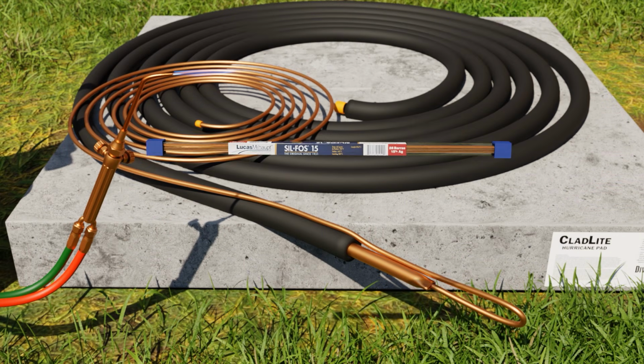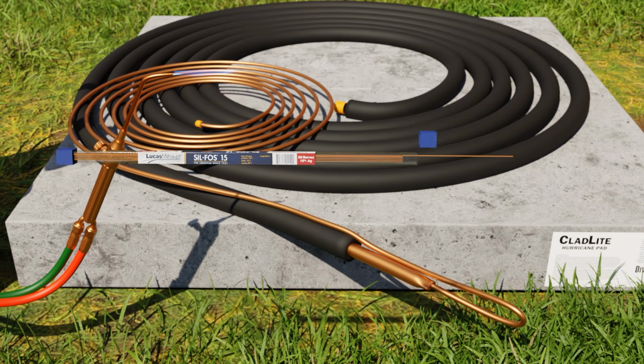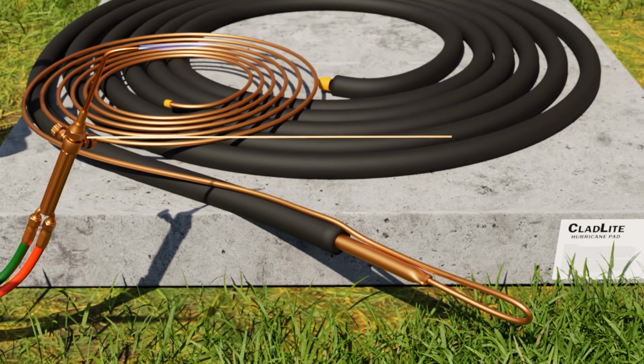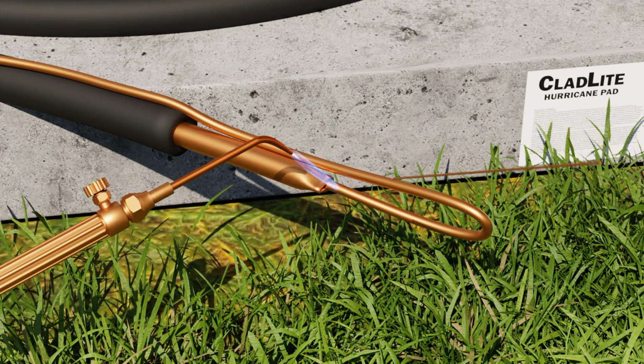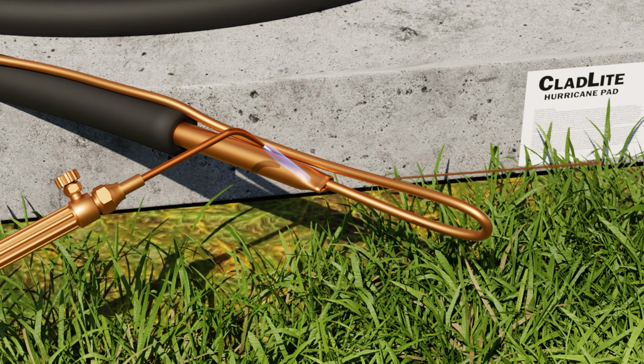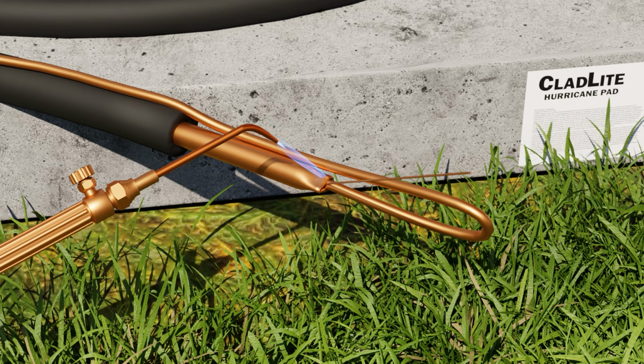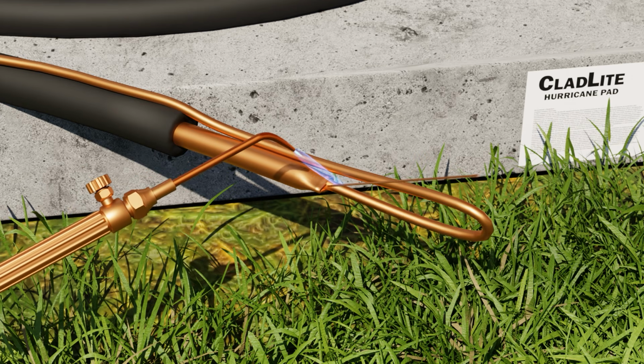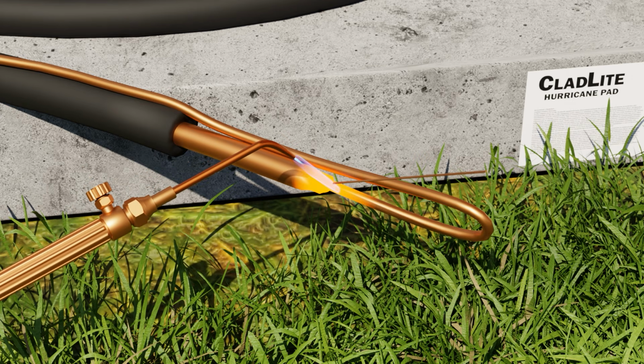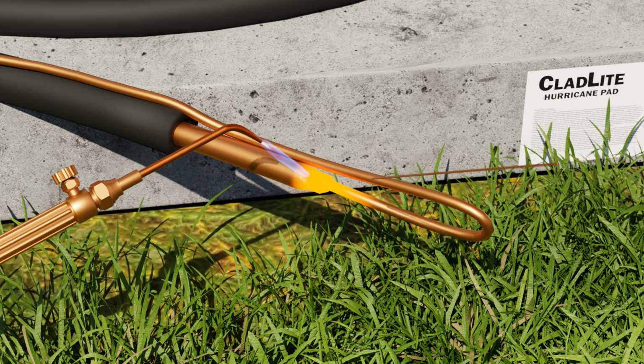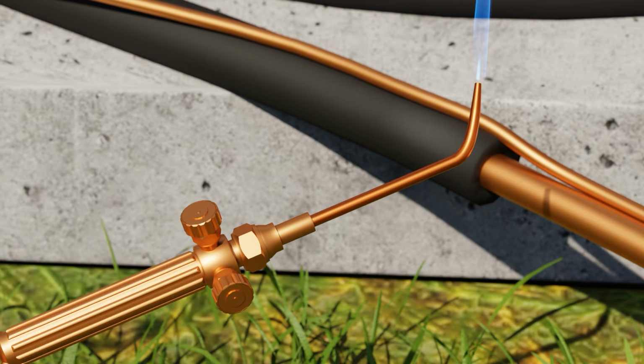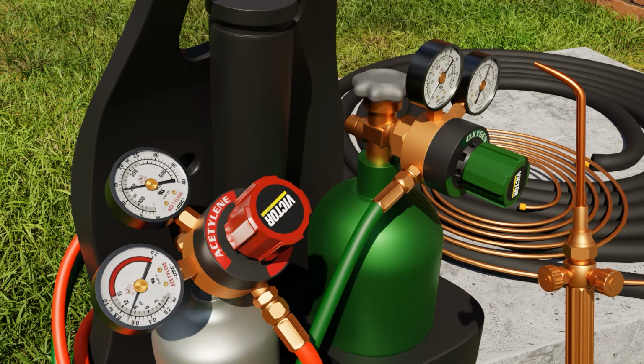We recommend using a 15% sil-phos rod, a silver and phosphorus alloy. Here we're showing that you heat the base material to dark cherry red and then apply brazing material. We do show this quickly. Some people will note that we did not flow nitrogen for this, and that's just because this section of the tubing is going to get cut off before we do anything with it. So nitrogen is a non-issue at this part of the process.